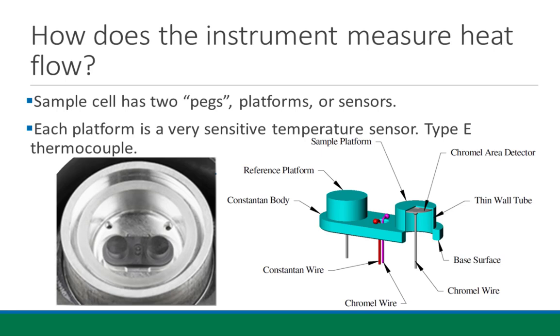The image on the right shows a diagram of the inside of these platforms. The junction of the two different metals is where temperature sensing takes place. In the cross-section of the peg, there is a chromel area detector fused to the constantan body, which is the bluish part. Where the chromel area detector and the sample platform are fused together is where the measurement occurs — it can measure temperature over that whole area. This happens at both pegs separately, and two more wires in the middle measure heat flow between the two platforms.